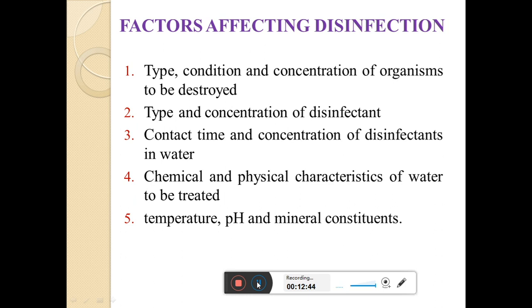And lastly, temperature, pH, and mineral constituents which are present in the water will also affect the disinfection. Temperature - the effect of temperature on the rate of killing bacteria is very important. As the temperature increases, the bacteria decreases or gets killed. pH value is also very important because the effectiveness of chlorine gets reduced with increasing pH values. The strong and effective hypochlorous acid is formed in greater quantities when the pH is low. At high pH values, less hypochlorous acid is formed. That's why temperature, pH value, and mineral constituents affect the disinfection efficiency.